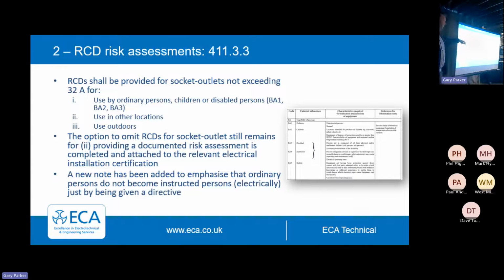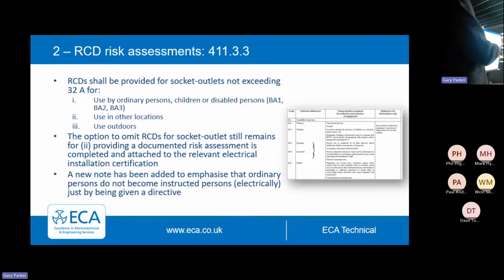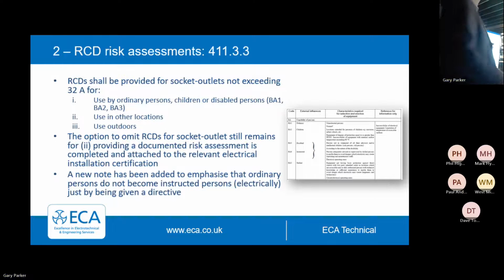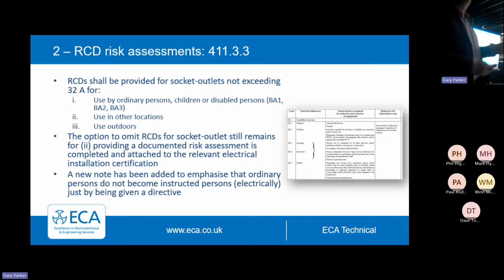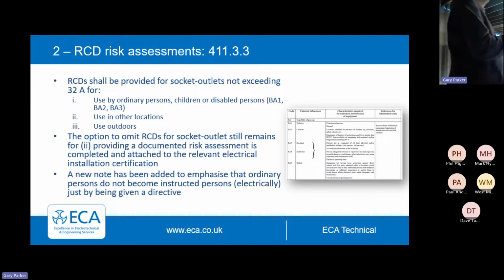There are 3 key areas where it talks about ordinary persons or children. You must put an RCD on socket outlets that are accessible, in other locations - which is a bit of a catch-all phrase - and outdoors. 1 and 3 must have RCDs. Nice and simple. 1 and 3 must have RCDs. Other locations, number 2, you can omit an RCD, providing there's a risk assessment for it.